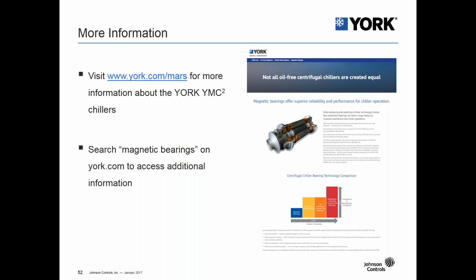Thank you, Craig. Another question is asking about retrofit. If someone has a YMC² chiller installed, can these chillers support the inverted operation, or is a new system required? That's a great question. There are no requirements on the chiller package itself to run inverted. You just need to start supplying colder tower water, turn it down, and let the system run.